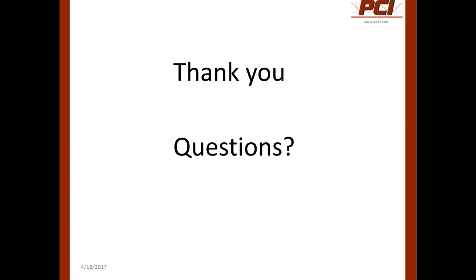So with that, that really is a brief overview of a very large project. I see one question as to the reason for the project, and there was a huge financial reason for it. With multiple ways of working, calibrations and doing that many calibrations was a very, very large cost for the organization. We had to find a way to streamline the calibration process, reduce the cost, but at the same time increase the quality of the program, because the old ways of working allowed way too many opportunities for human intervention and mistakes to be made. So by taking the process, moving it towards paperless, applying a risk-based approach, we were actually able to reduce our calibration cost by over 30% within the first calendar year that the project was deployed.